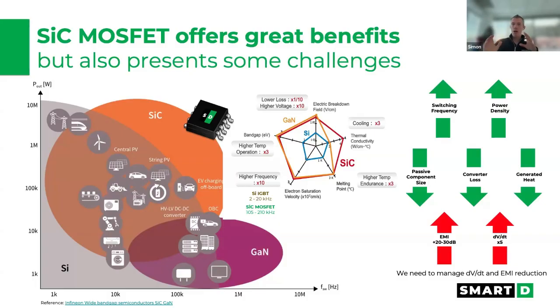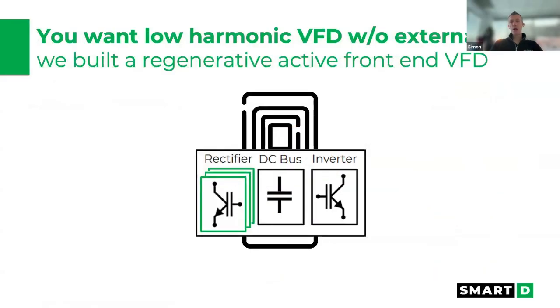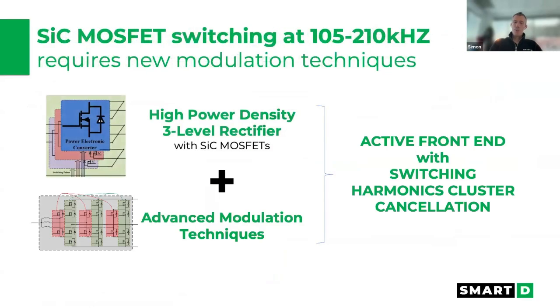So if you simply apply these new materials, whether it's silicon carbide or gallium nitride, to your existing architecture, you're going to encounter problems and you won't be able to use it as is. So this is where at SmartD, we had to reinvent the VFD. Yes, we wanted an active front end to get all those benefits of low harmonics and regen capability. But we use silicon carbide on it, and we use it at a super high switching frequency, running at 105 kilohertz, using completely new modulation techniques.